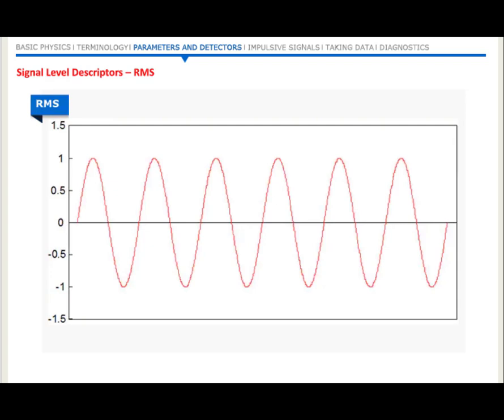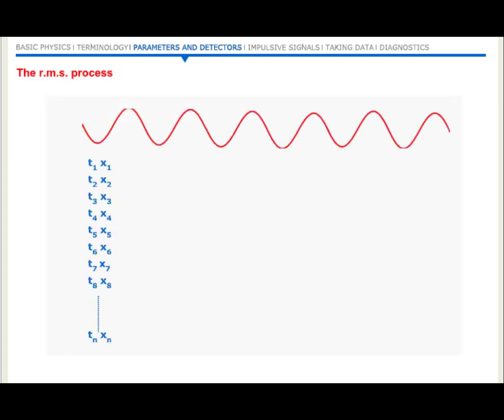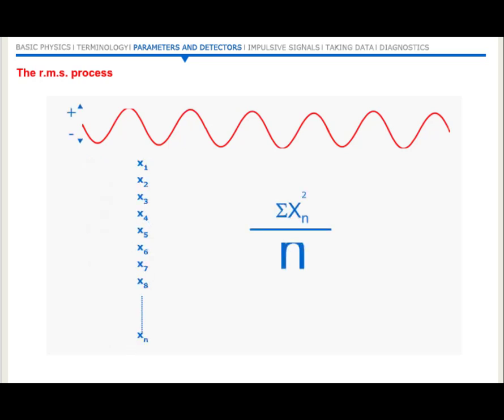It's a way of averaging the signal, so let's take a little time to understand it in more detail. The RMS value is calculated by taking a series of amplitude measurements over a period of time. For example, 1024 measurements over 400 milliseconds. The simple average, or mean value of these measurements would be 0, because for half of the cycle the values are positive, and for the other half of the cycle they are negative. Square each value and then take the average or mean. When the negative values are squared, they become positive values. Take the square root of the mean value and that gives the RMS.